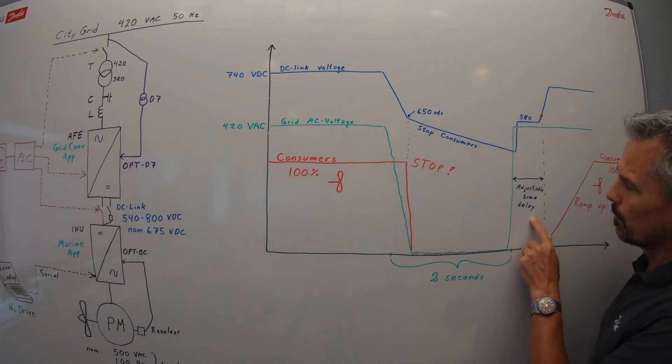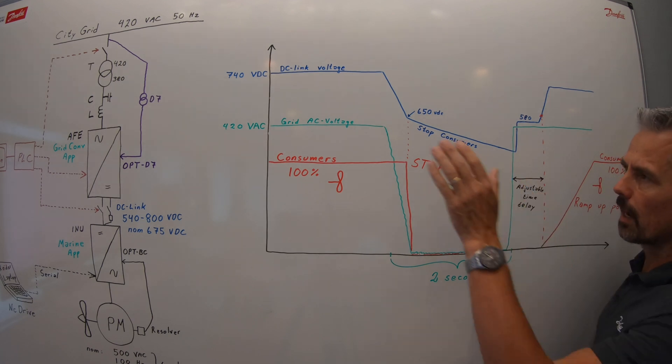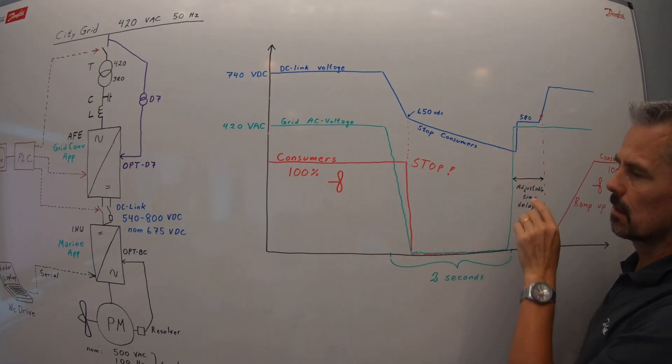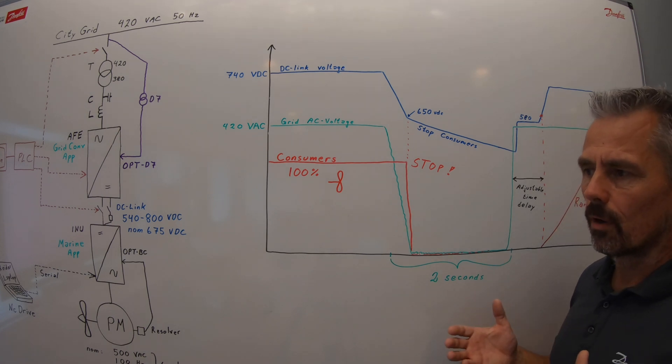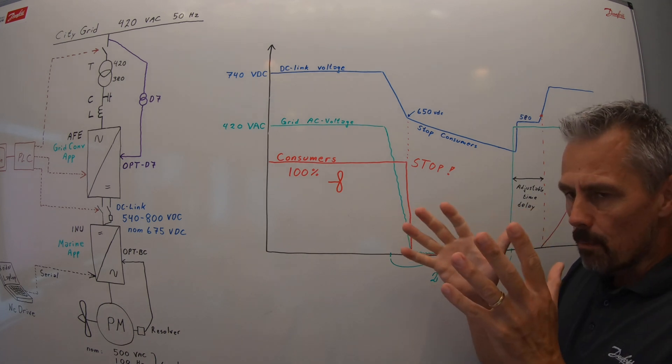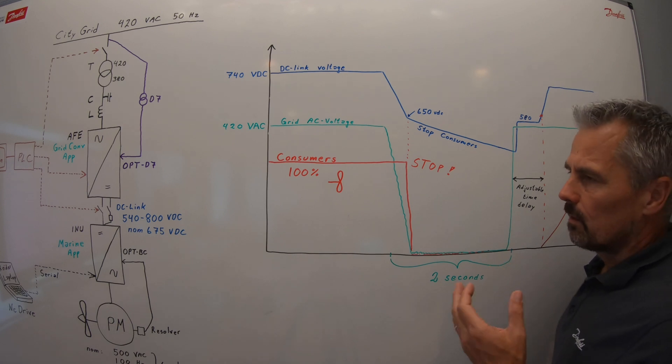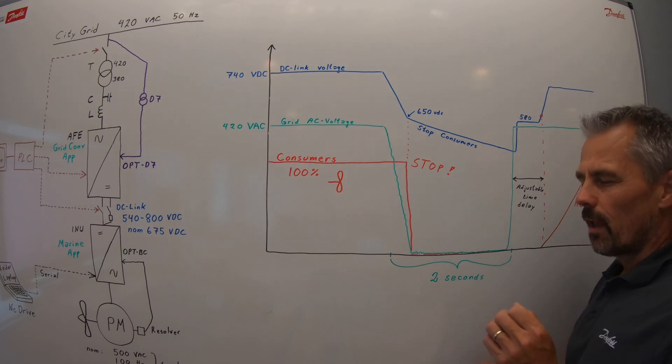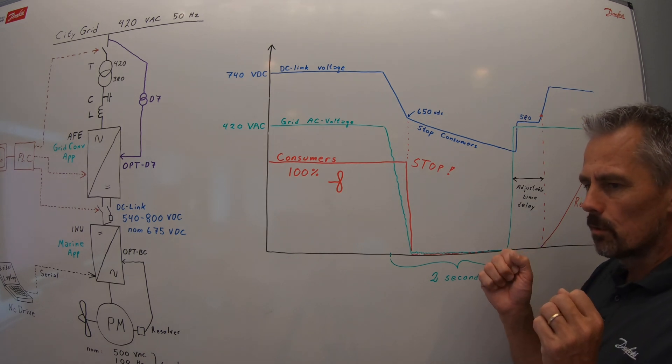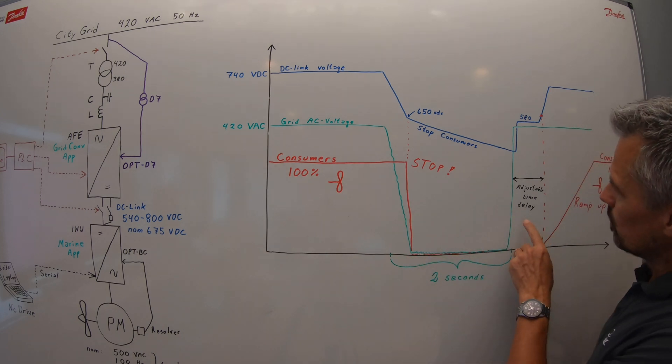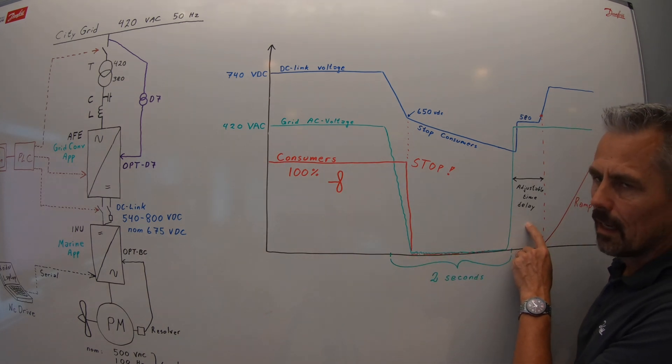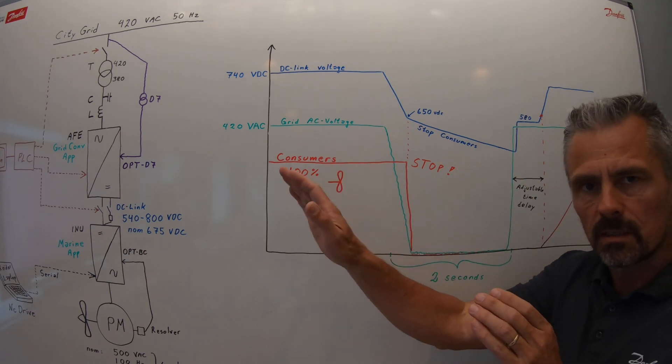And note, there is also an optional, from parameter, adjustable time delay for the active frontend to restart. Why is that? If you have four big propulsion units, you don't want to have them to start on the same time. And the diesel generators and also the grid converters from battery supply will suffer if everybody, all the propulsion units, kicks in at exactly the same time.